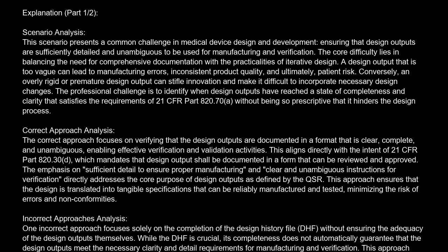The emphasis on sufficient detail to ensure proper manufacturing and clear and unambiguous instructions for verification directly addresses the core purpose of design outputs as defined by the QSR. This approach ensures that the design is translated into tangible specifications that can be reliably manufactured and tested, minimizing the risk of errors and nonconformities.